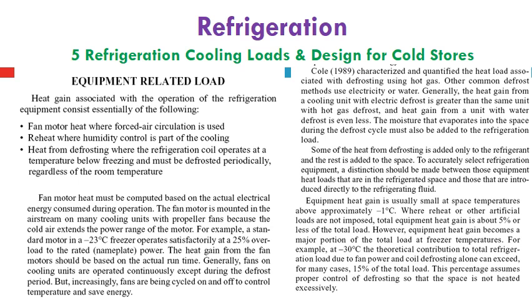Cole in 1989 characterized and quantified the heat load associated with defrosting using hot gas. Sometimes we can use defrosting by hot gas bypass from the discharge of the compressor, which is at the highest temperature. We can re-inject it at the entrance of the evaporator to make it hotter, and then the frost melts on this coil instead of using an electrical heater as an additional external load, by using the hot gas of the refrigerant at the discharge temperature of the compressor.